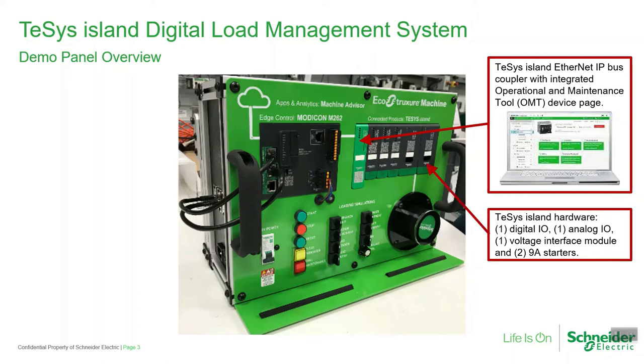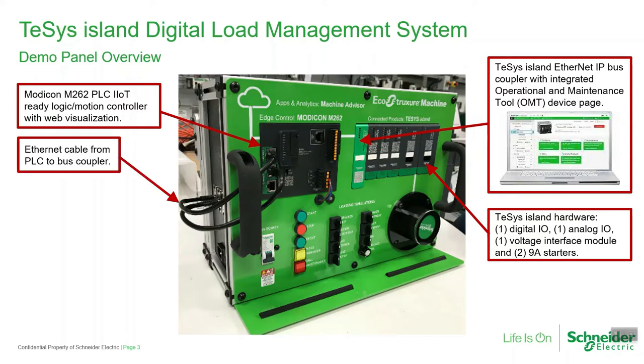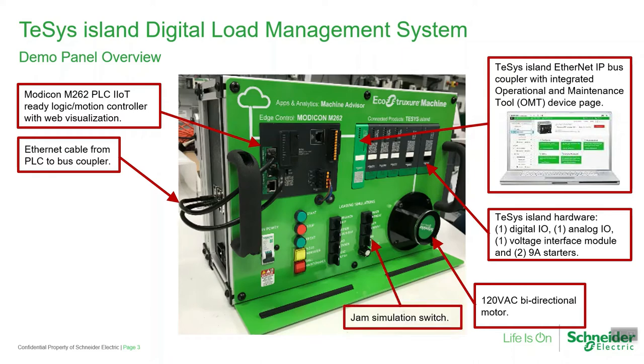The TeSys Island hardware includes one digital I/O, one analog I/O, one voltage interface module, and two 9-amp starters. The island is connected to a Modicon M262 PLC. We're using an Ethernet cable to connect the PLC to the island. Our load is a 120-volt bidirectional motor.